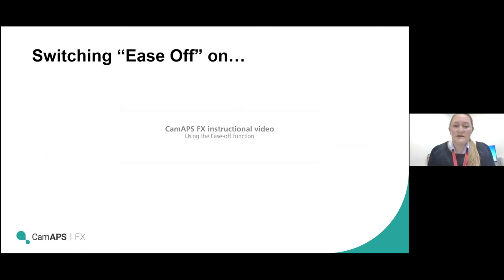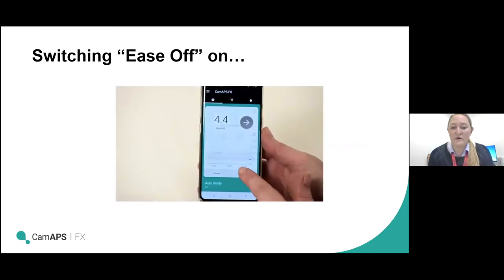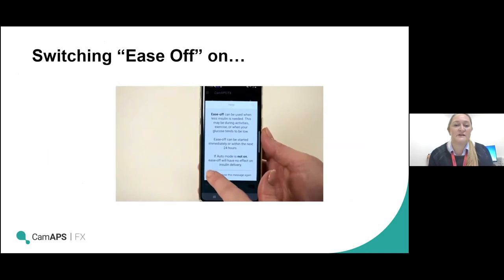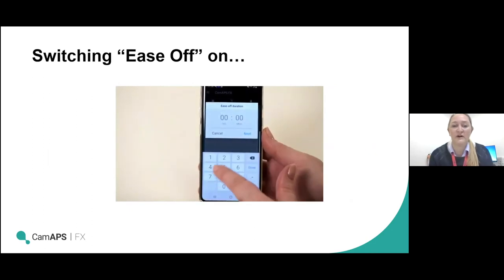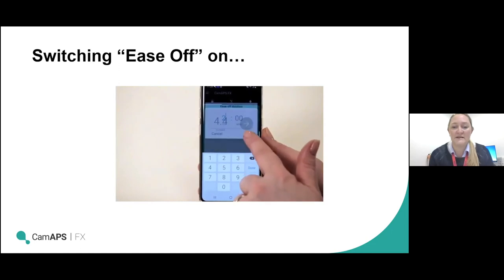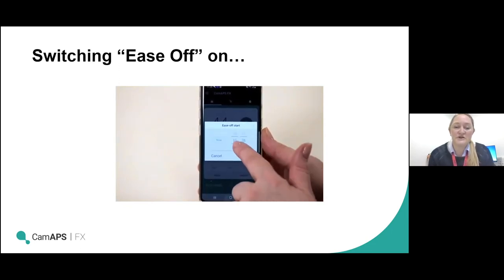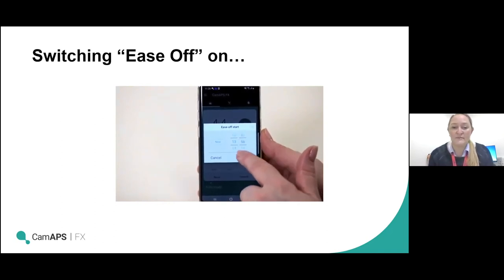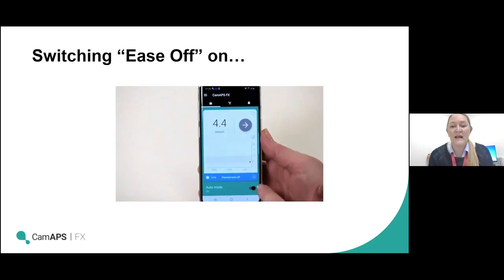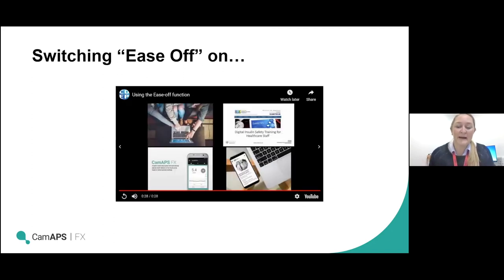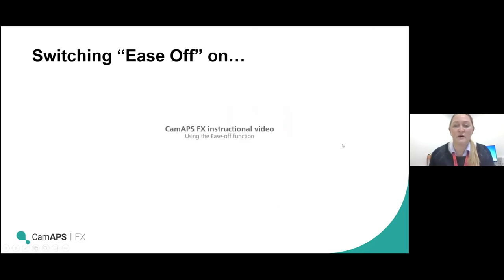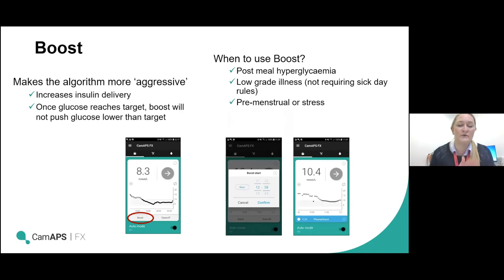In the ease off video, you can see that by touching the ease off button it tells you what ease off does and when it might be useful, then asks how long you want it to run. Entering two hours and pressing next, it asks whether you want it now or later. If you choose later, it lets you preset the time you want it to come on. You can see 'planned ease off' with a little clock icon indicating it's set to come on automatically at the programmed time, relative to the exercise period.